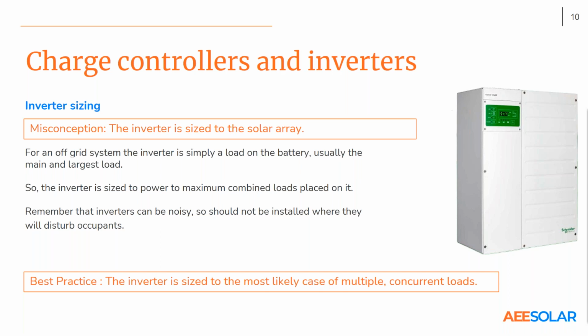I don't know if anybody listens to AM radio anymore, but it was an issue, or had been an issue. One way to reduce that is to take the battery cables between the battery and the inverter and keep them as close together as possible. Ideally they'd be twisted pair, but that's a little impractical with 2-aught and 4-aught cable. Just keeping them together does help reduce that somewhat.